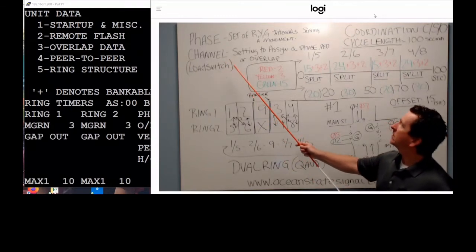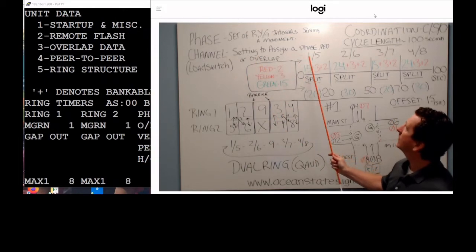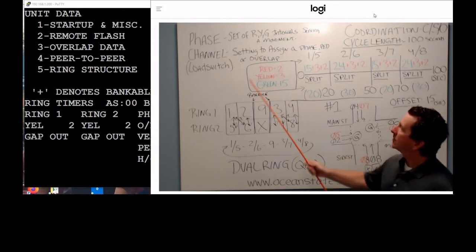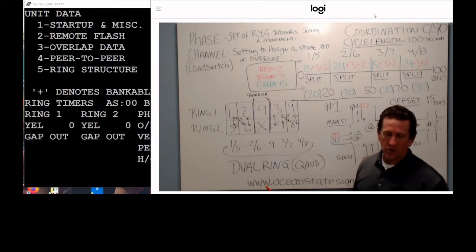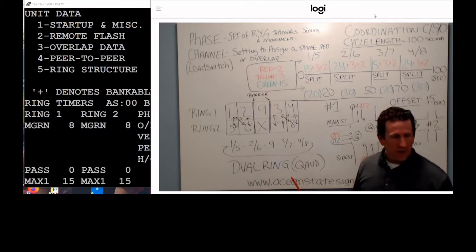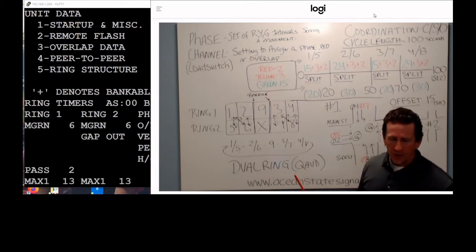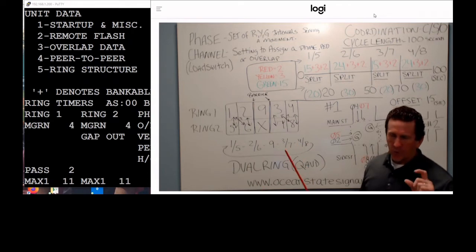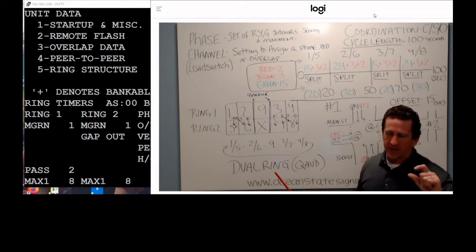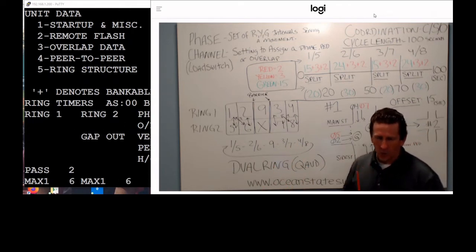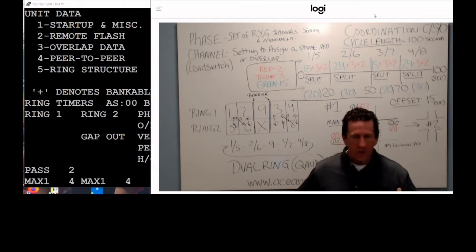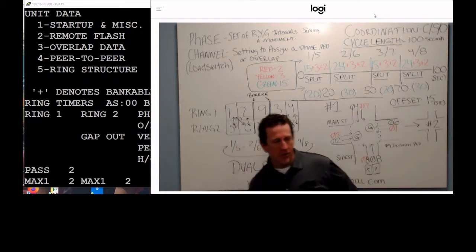And then we're going to have a channel. A channel is a setting to assign a phase, PED, or overlap to. Channels and load switches go together, okay? So you'll see as we go through this that we put phase assignments, we put phases into channel assignments. They're two totally different things. So I'm going to try to demonstrate that today so we'll have a better understanding.